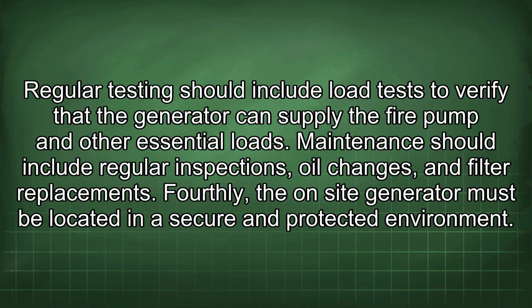Thirdly, the on-site generator must be regularly tested and maintained to ensure that it is in good working condition. Regular testing should include load tests to verify that the generator can supply the fire pump and other essential loads. Maintenance should include regular inspections, oil changes, and filter replacements.